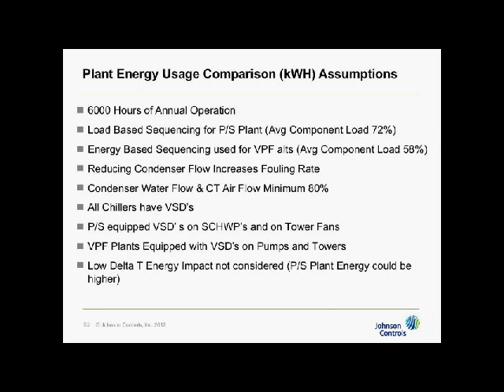We assume 6,000 hours of annual operation, and we assume load-based sequencing for a primary-secondary plant. When you do that, the average component load varies, of course, but it's going to be around 70%. In our case, it landed at 72%. For a VPF, we're going to assume energy-based sequencing, and when you use energy-based sequencing or a CPO type of control, the average component load drops. In this case, it ended at 58%.